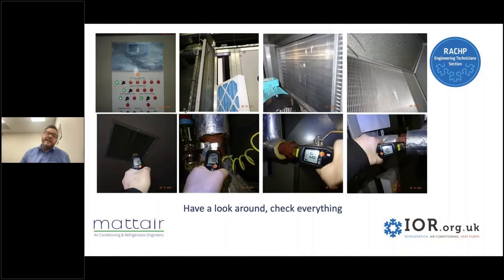Another one I want to look at, I just want to share this picture, is another case of your behavior affecting my behavior, and it's how the plant working in one way will affect the plant in another way. Looking at the top picture, this is an air handler attached to boilers and also to a chiller. On the left-hand side, everything looks okay: no faults on the BMS, the filters are fine. You look inside, this is a 15-year-old air handler, and it's in pretty good fettle, to be fair. The coil's clean, the heat exchanger's clean.